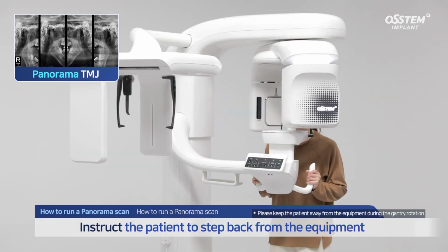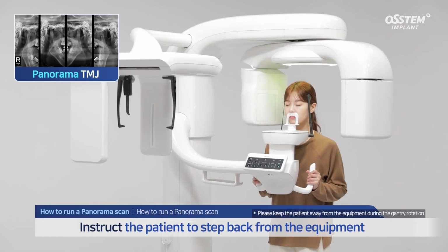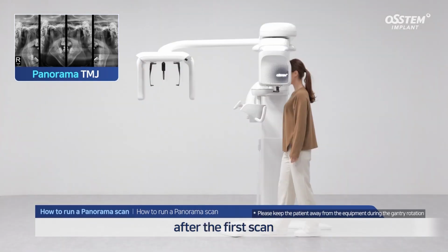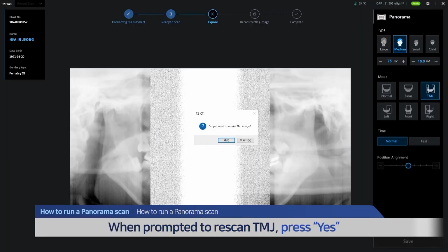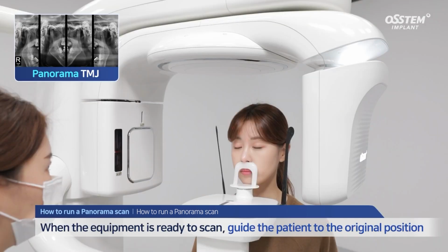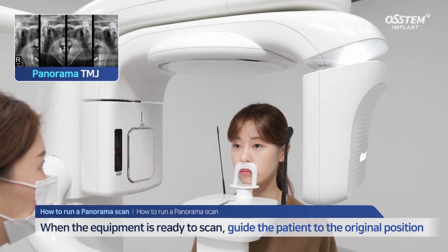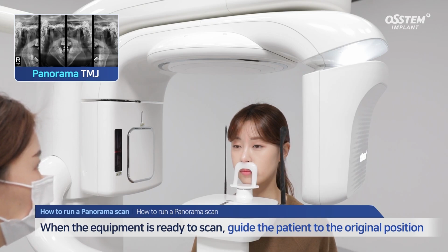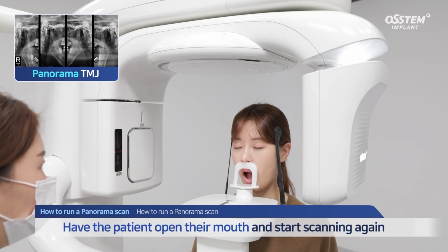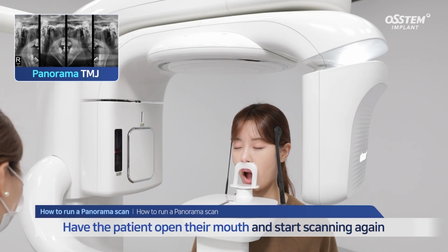Complete the first rotation of scanning with the mouth closed and have the patient step back from the equipment. When prompted to rescan TMJ, press yes. When the equipment pauses its operation, position the patient in the same manner as before. Then, have the patient open mouth and start scanning one more time.